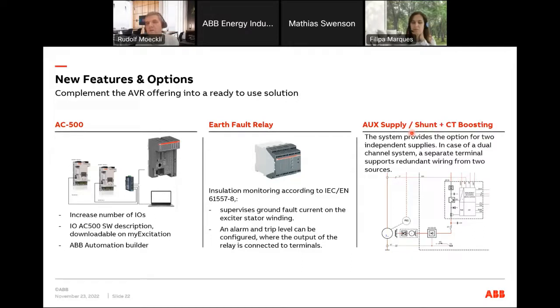Especially when you have the shunt supply, please remember you have to fulfill fault ride-through capability. That means in a shunt supply, your supply comes from the generator side. If you have a short circuit on the network, this supply will go to zero, and therefore you need CT boosting to push up excitation voltage.